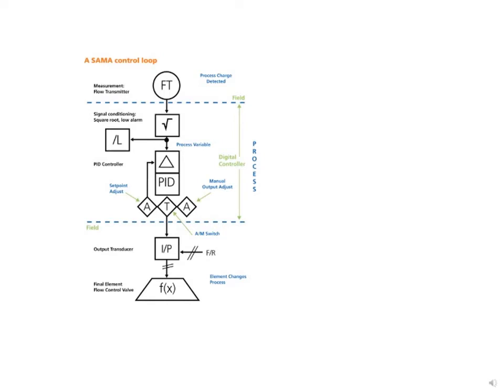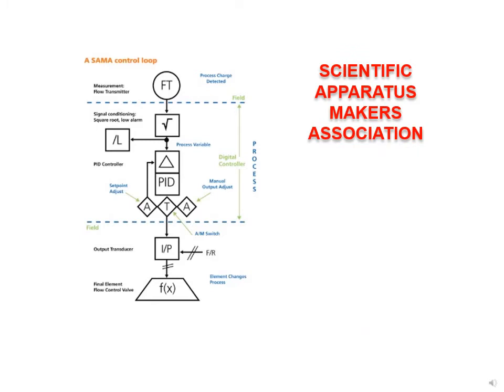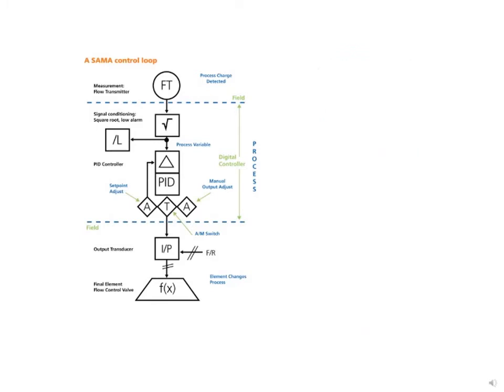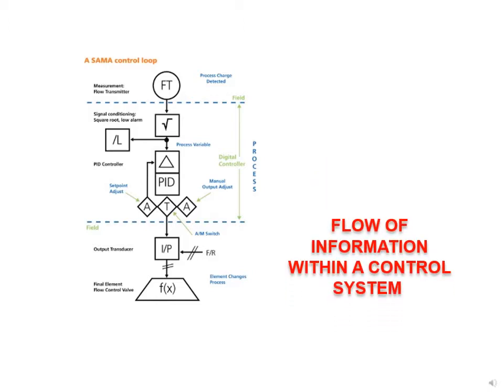SAMA is an acronym standing for Scientific Apparatus Makers Association, referring to a unique form of diagram used primarily in the power generation industry to document control strategies. These diagrams focus on the flow of information within a control system rather than the process piping or instrument interconnections.